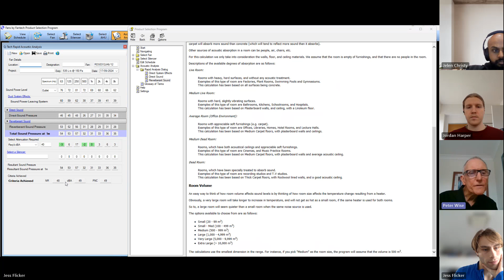So you've put in some figures there that are fairly relevant to what we're doing. If you put in 55 as the required dBA, it's saying you need attenuation at 250 hertz of 2 dB, but it's also saying we've achieved 49 dBA here. So this is, I guess, what I was saying before about low frequency noises being an issue.